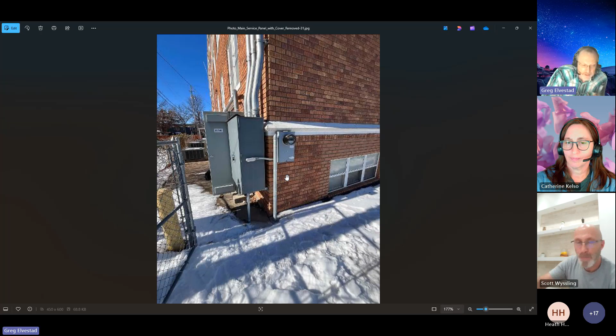That defined working space is roughly the size of your kitchen fridge: 6.5 foot tall, 30 inches wide, 3 foot deep. If you can't park a fridge against the wall and not have it tip over where you plan to put some equipment, do not attempt to put electrical equipment on that wall. It's not code compliant. The platform where you need to work has to be flat.